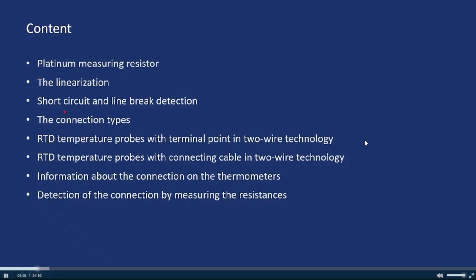Then I have information for you about short circuit and line break detection. This works very well with RTD temperature probes. And then I want to spend a little time on the connection types. Maybe you know that we can connect the probes in 2-wire, 3-wire, 4-wire. I want to show you the differences and the drawbacks sometimes, or what is better if you use the one or the other technology.